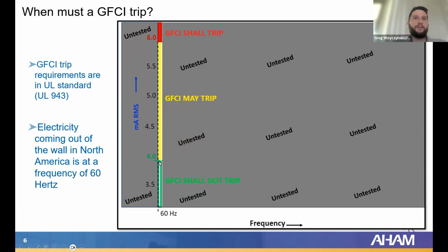If a GFCI measures a 60 hertz differential current of 4 milliamps or less, it shall not trip. In order to get its UL approval, it cannot trip. UL will give it some signals at less than 4 milliamps. And if it trips at 4 milliamps or less, then it's no good. It cannot get UL 943 certification. If a GFCI senses a 60 hertz differential current between 4 milliamps and 6 milliamps, the GFCI may trip. It's up to the individual GFCI manufacturer to decide that. If the GFCI sees that signal of 6 milliamps or greater, it has to trip. It must trip in order to comply with that UL standard.